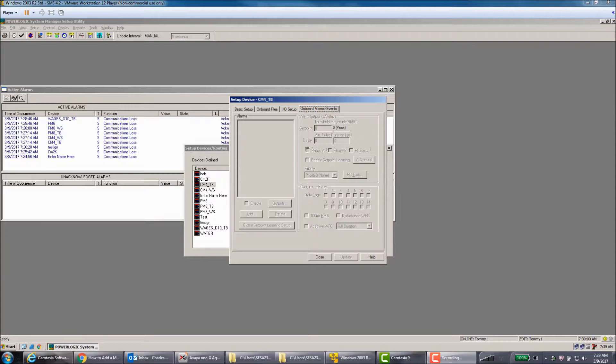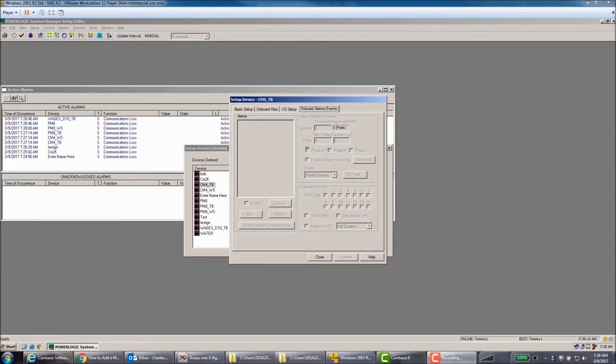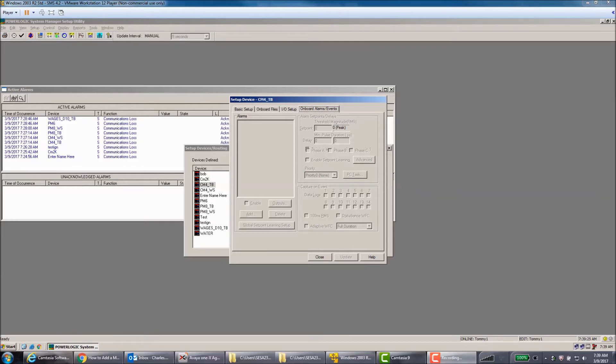Once that opens, you'll go to the Onboard Alarms and Events page. From here, when you're communicating, these will not be grayed out and you can click the PC Task and select your mail task on an alarm that you've set up. So, for example, if I wanted to do an alarm for voltage, I would go to my voltage alarm and set it up and trigger the PC task when that alarm occurs. That way you'll get an email notification letting you know that you have a voltage problem on this particular device.